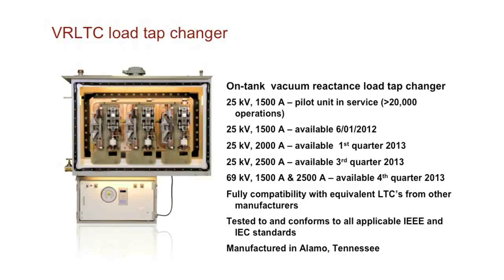Basically, we've got it out there in service now. It's an on-tank vacuum reactance load tap changer. Right now we have the 25 kV 1500 amp that's out there. It's been out there for a while. It's got about 21,000 operations and it's just hum along just fine. There's production on that one. It starts June 1st this year.